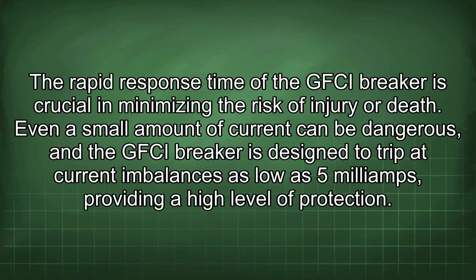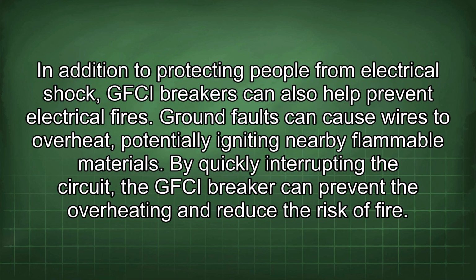The rapid response time of the GFCI breaker is crucial in minimizing the risk of injury or death. Even a small amount of current can be dangerous, and the GFCI breaker is designed to trip at current imbalances as low as 5 mA, providing a high level of protection. In addition to protecting people from electrical shock, GFCI breakers can also help prevent electrical fires. Ground faults can cause wires to overheat, potentially igniting nearby flammable materials. By quickly interrupting the circuit, the GFCI breaker can prevent the overheating and reduce the risk of fire.